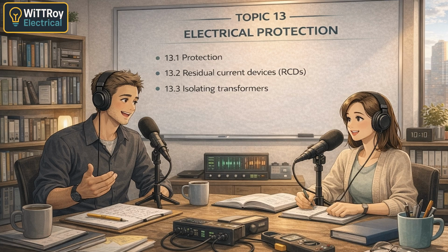Now let's talk about testing. How do we confirm an RCD works correctly? Using an RCD tester. Correct. What tests are performed? It must not trip at half rated current. Yes. It must trip within time at rated current. Correct. And it must trip within time at 5 times rated current. Yes. And at which phase angles? 0 and 180 degrees. Correct. If it fails any test? It's electrically unsafe and must be replaced.